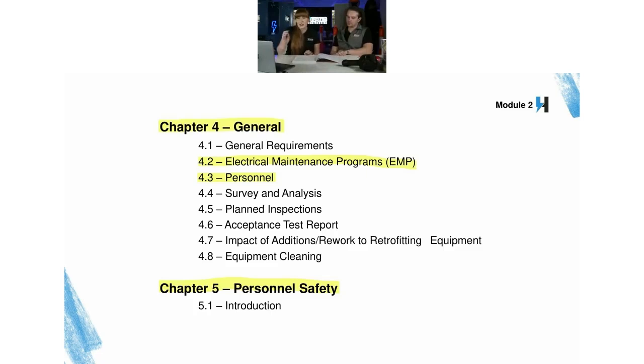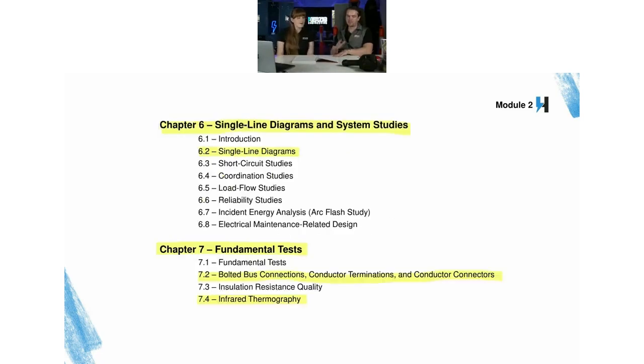Next, moving on, we have chapter 6, and being an engineer, this is probably my favorite chapter. Absolutely. This is our bread and butter section right here. So highlight the single line diagrams. You must have these, and they should be legible and documented. You've got short circuit studies, coordination studies, load flow studies, reliability studies, and finally arc flash studies, all of which should be reviewed for accuracy at intervals not to exceed 5 years.